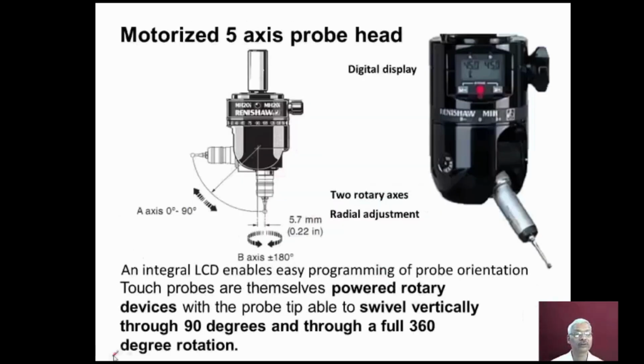Now you can observe a motorized 5-axis probe head here. This is the probe head, and appropriate styluses can be inserted into the probe head. We can observe here that apart from XYZ motion given by the CMM structure, these motorized probe heads have their own A-axis movement as well as B-axis movement. So the stylus can be swiveled as shown here, and the stylus can rotate in plus 180 degree or minus 180 degree. Apart from that, a radial adjustment is also possible.